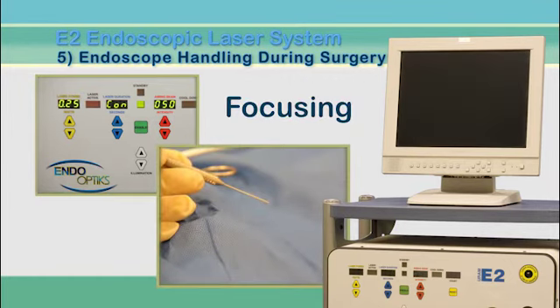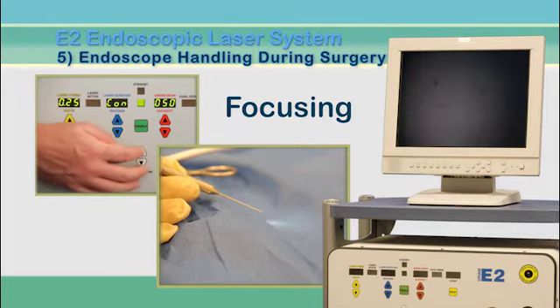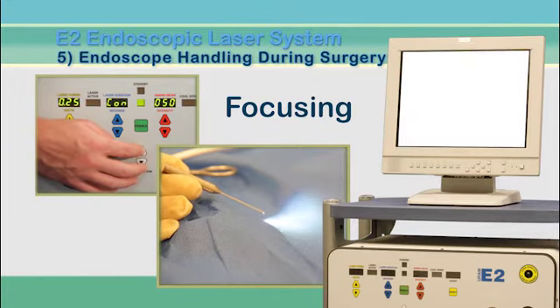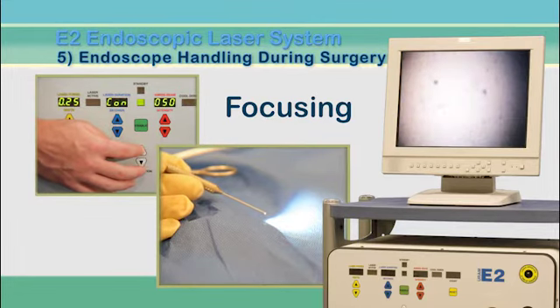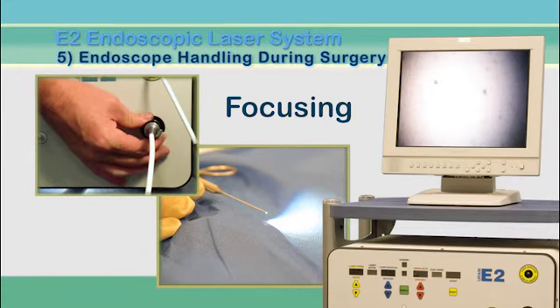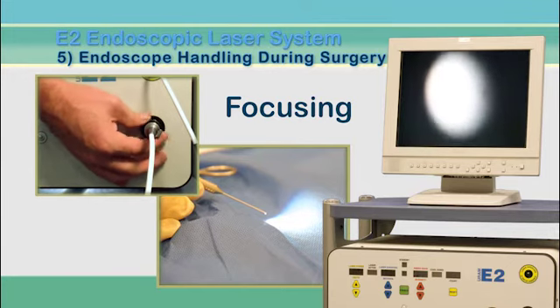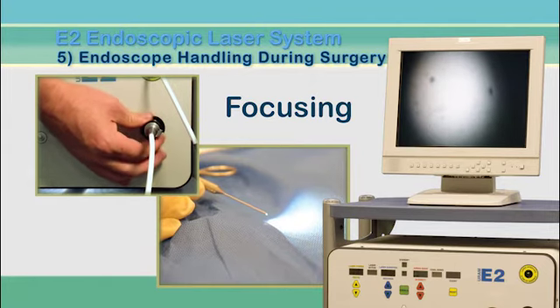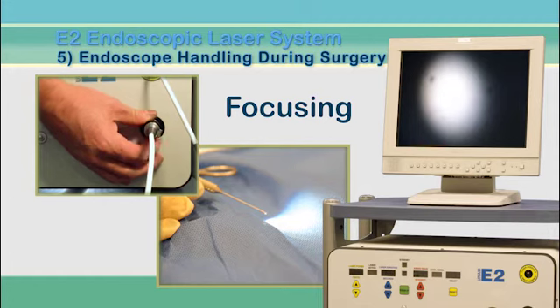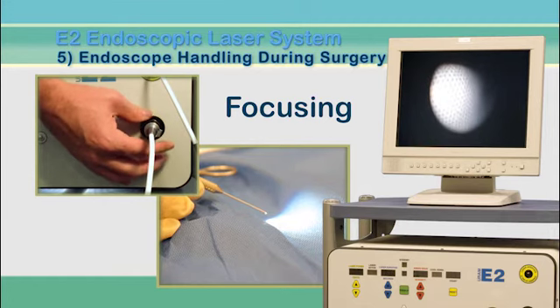Now you're ready to focus the image. With the handpiece placed securely on the sterile drape, aim the tip at a piece of the cloth. Begin by pressing and holding the up arrow to increase the illumination. You will see light from the tip of the endoscope and on the monitor's image circle. Bring the image into focus by rotating the focus ring on the video coupler. If the white circle on the screen is getting smaller, keep turning until the image is in focus. If the circle is disappearing, turn the ring in the opposite direction until an image begins to appear. Perfect focus is reached when the edge of the image is a sharp and crisp line.